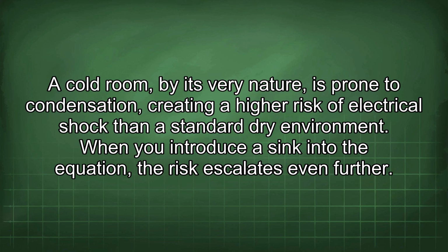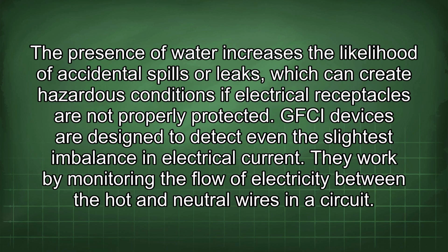A cold room, by its very nature, is prone to condensation, creating a higher risk of electrical shock than a standard dry environment. When you introduce a sink into the equation, the risk escalates even further. The presence of water increases the likelihood of accidental spills or leaks, which can create hazardous conditions if electrical receptacles are not properly protected. GFCI devices are designed to detect even the slightest imbalance in electrical current. They work by monitoring the flow of electricity between the hot and neutral wires in a circuit.